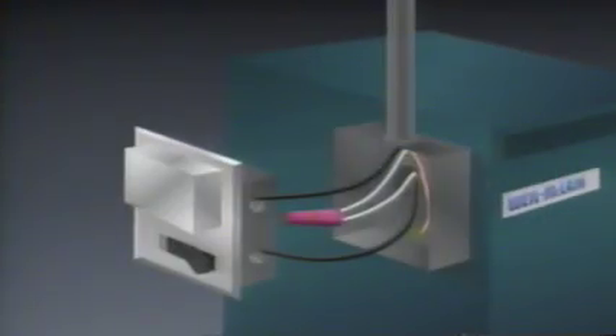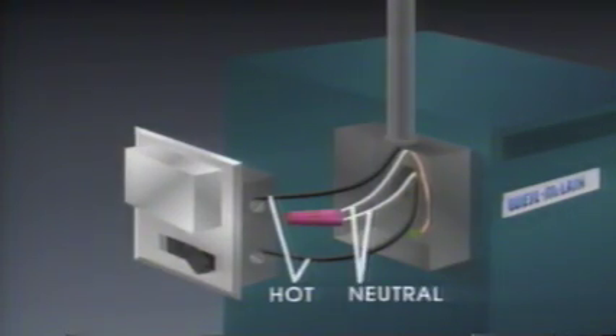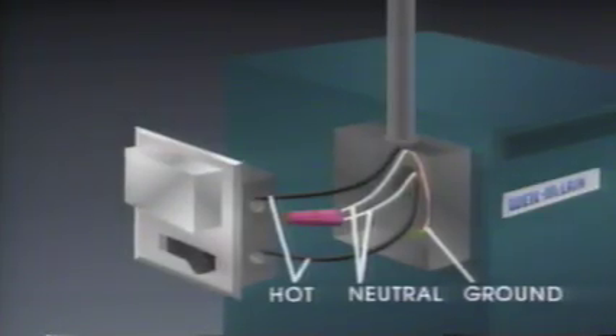With all of this in mind, let's look at providing power to a typical boiler from the service switch. The same principles apply as with our basic electric circuit. The black hot wire from the circuit and the black wire from the boiler are attached to the switch. And the white neutral wire from the boiler is attached to the white wire of the circuit using a wire nut. The ground wire is grounded to the grounding screw on the service switch or metal J box. And that's all there is to it.